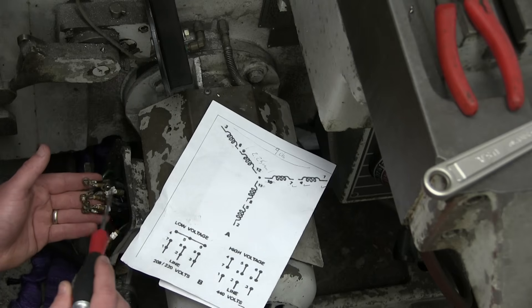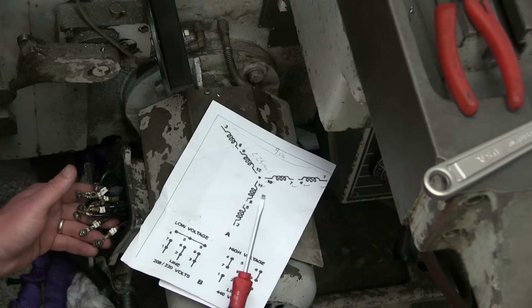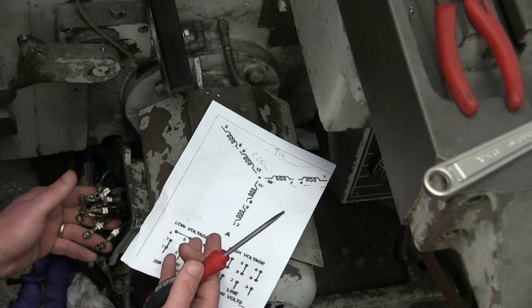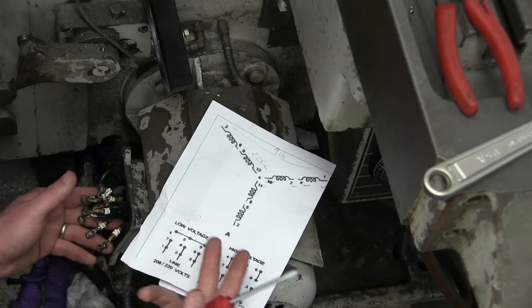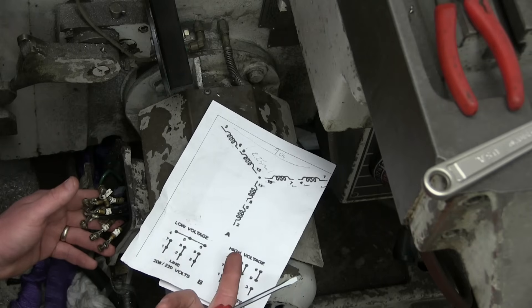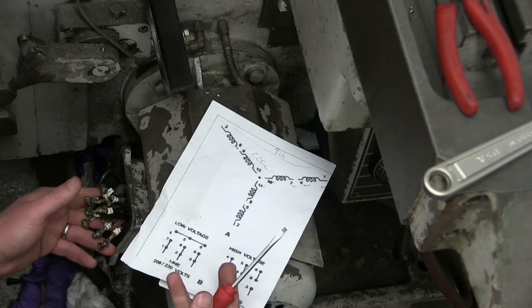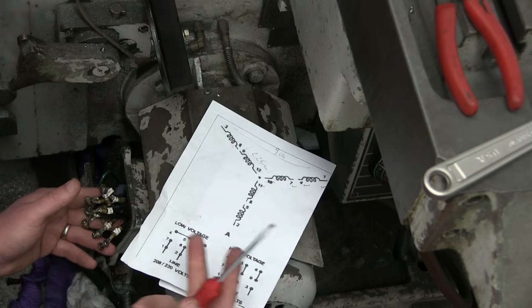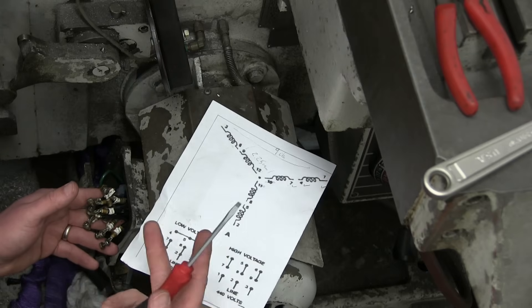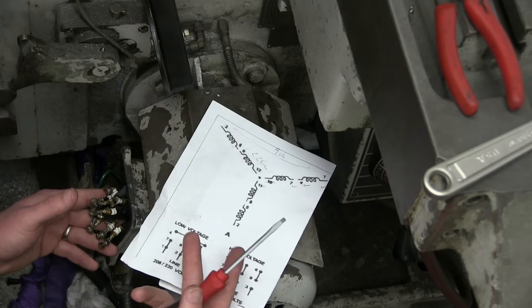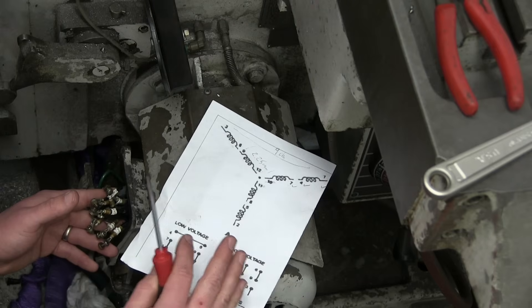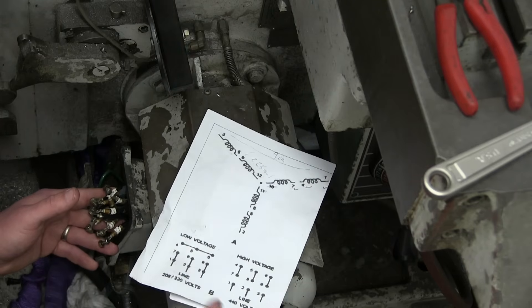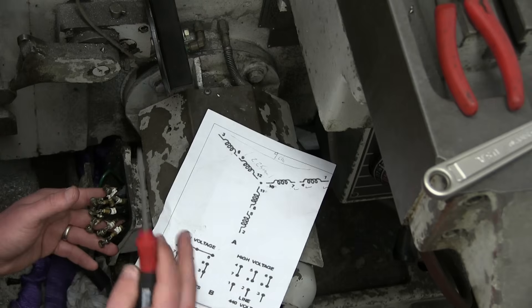So that's the hard part done. Now as far as the audit goes, we're getting a variable frequency drive, 220 volts. Why 220 volts? Because we don't need to get an auto transformer, don't need to buy additional transformer. Why not a rotary phase converter or a static phase converter? One, there's a wild leg where the voltage is all over the place. It goes one phase in, three phase out, but one of those phases is craptacular. You only get two-thirds of the power out of it, and they're expensive. Antiquated technology, they're more expensive than the vector drive. Unless you have a specific usage case for a rotary phase converter, it's not worth it. Lean towards the new technology, the variable frequency drive.